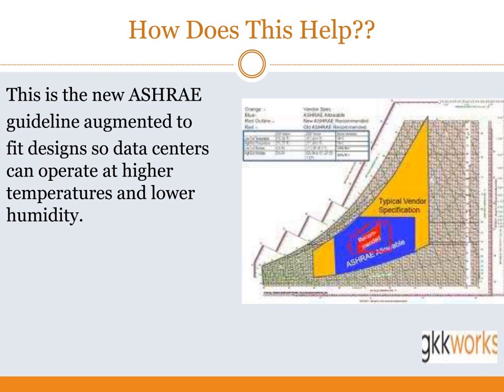And how does this help? The new ASHRAE guidelines have come out, as Julius detailed in his piece of the presentation quite adequately, and we're now resolving these issues by widening an envelope, by dictating that it's okay to operate the data center facility at a higher temperature. But are we decreasing the amount of space that we're utilizing to develop data center facilities based on these new requirements that are coming from ASHRAE?